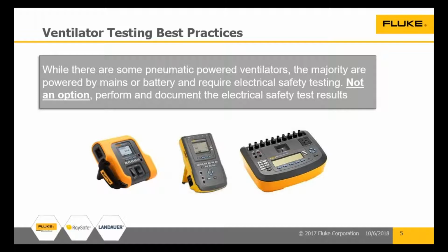Okay. What does the manufacturer test procedure from the service manual point you to in terms of what electrical safety standard you're supposed to test against? Like on a Draeger, there's a couple different ones. I can't cite the name, but it's like IEC. IEC, so they're an international standard. Okay, well, let me give you some help with that. There are two different ones. One is focused on the manufacturer and everything could include your incoming inspection. But at that point, you're allowed to use 62353, which is much abbreviated in terms of the tests that have to be done on it, right? So that's one thing. Okay, so we know that.